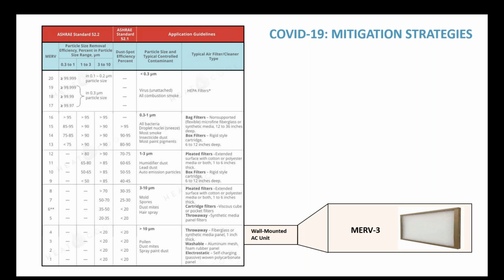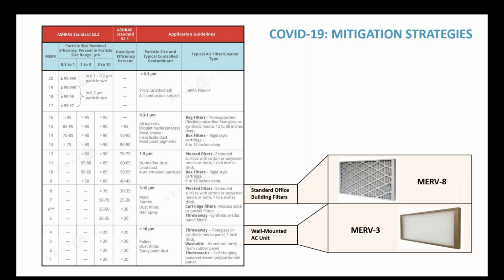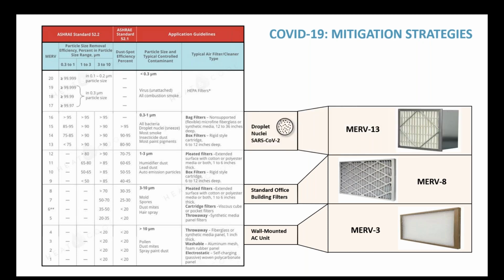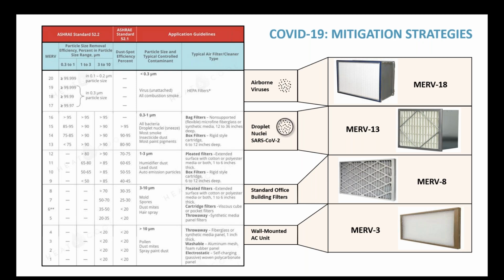So just a real quick refresher on filters in general. If you're not familiar with what a MERV 13 or 14 filter is: MERV 3, which is extremely low, is something you might find in a window unit or a wall-mounted unit. MERV 8, which used to be the standard for office buildings, is increased efficiency, but is really just focusing on the very largest particle sizes, visible dust, things of that nature. MERV 13 is where you're starting to get into the droplet nuclei and virus capture. And then above that, you're really talking about HEPA filters. HEPA filters are really a leap from MERV 13 or 14, because to even be considered HEPA, these filters have to be 99.9% efficient at the 0.3 micron particle size, which is very, very small. And so you may be thinking, oh, this is great.